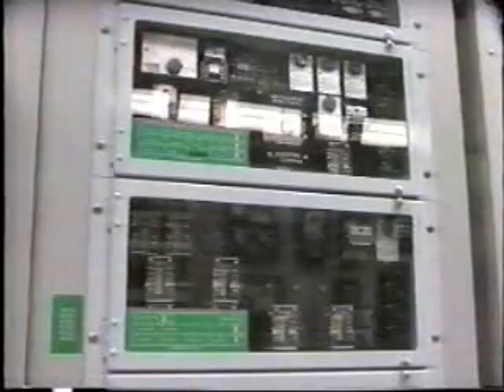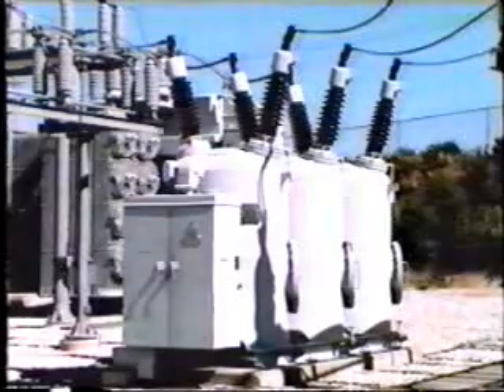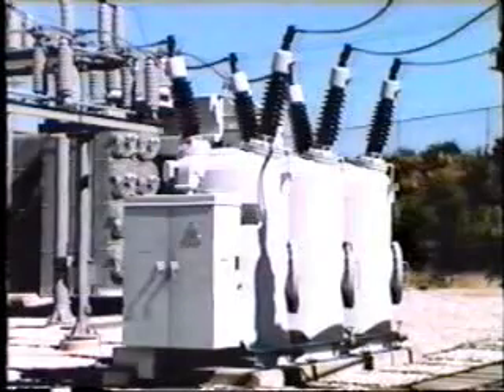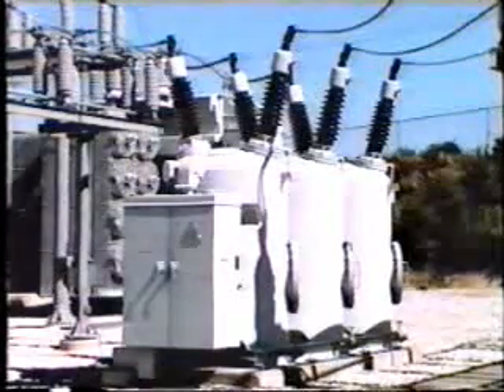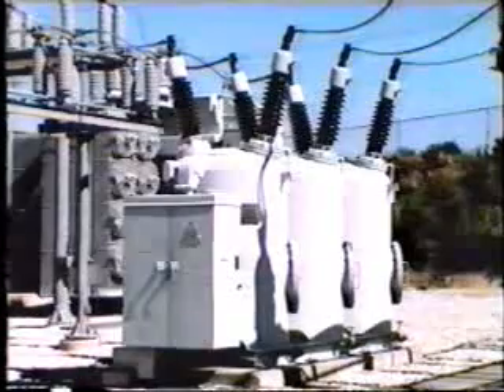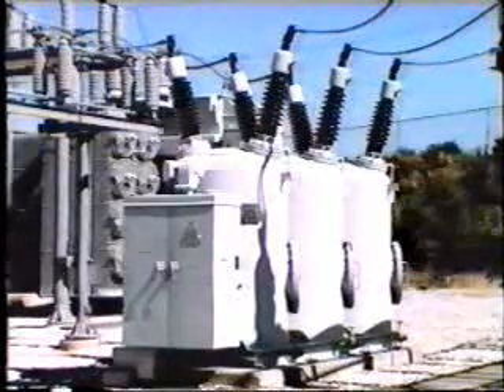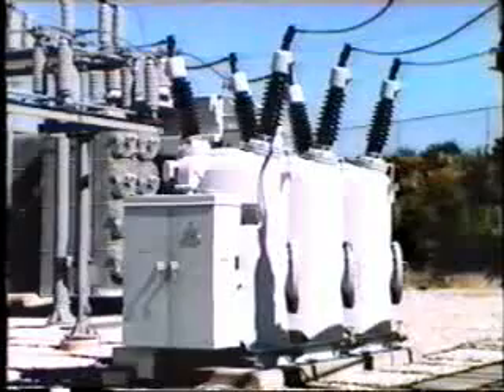Clearing the fault is important, not so much to prevent damage to the line as to prevent damage to the equipment, that is, generators and transformers, which are supplying power to the faulted line. The protection scheme must be designed and set so as to trip the breakers feeding the faulted line, but to leave the remainder of the system operating intact. You will remember we have already discussed in earlier tapes the need for sensitivity and selectivity of protection schemes.